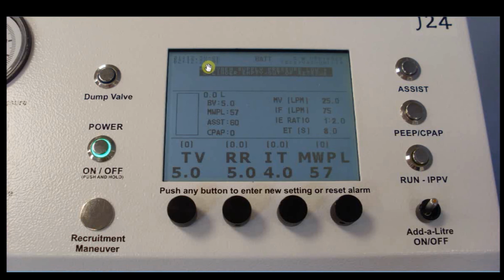If any of them gets to a low or critical value, it'll show here on the screen and also be indicated by a warning error that will flash up in this area of the screen here. To the right of the battery symbol or battery name, we have the software version, which on this one is 6025, and then in brackets we have a number which in most instances will be increasing, and that's the time between the vacuum pump running.